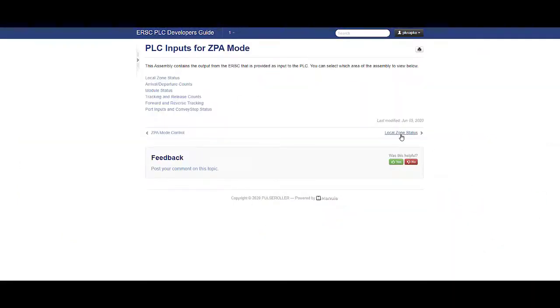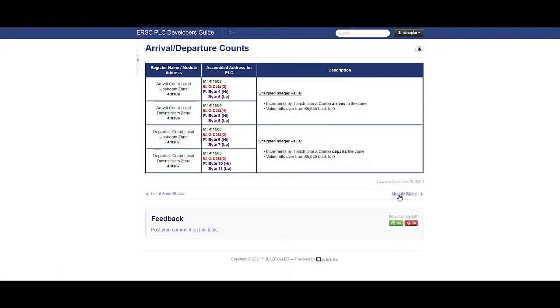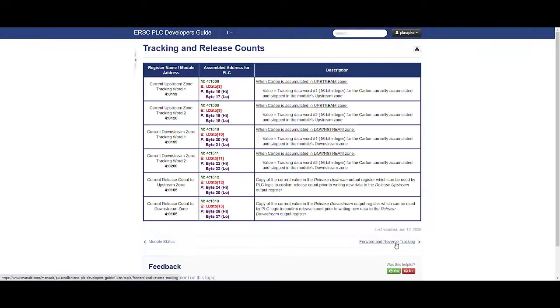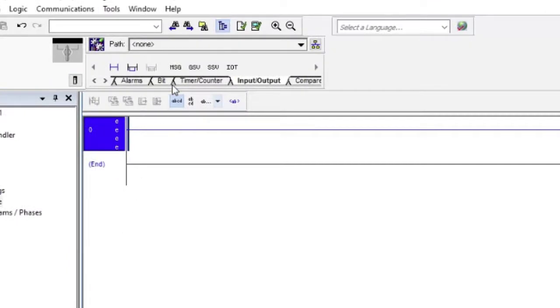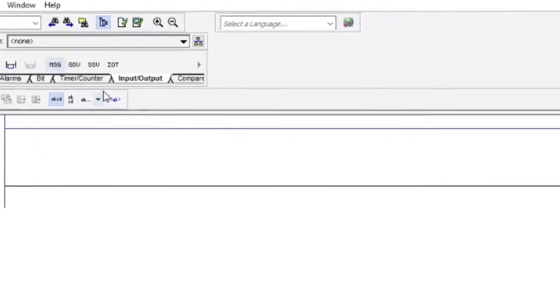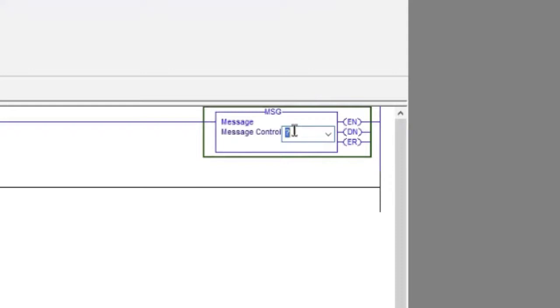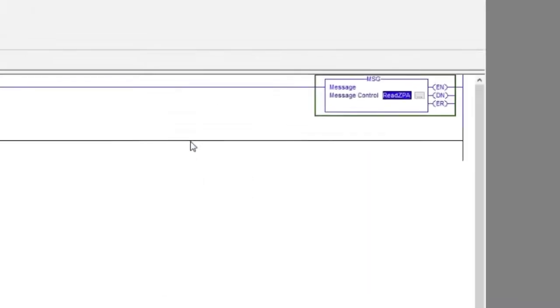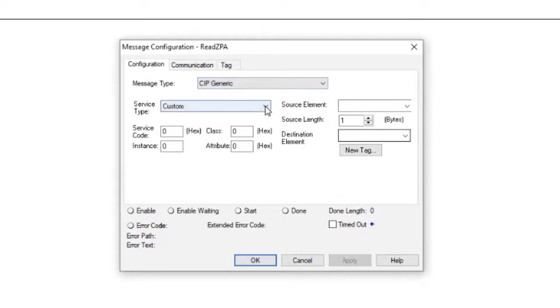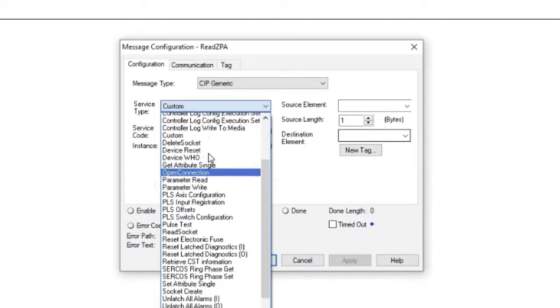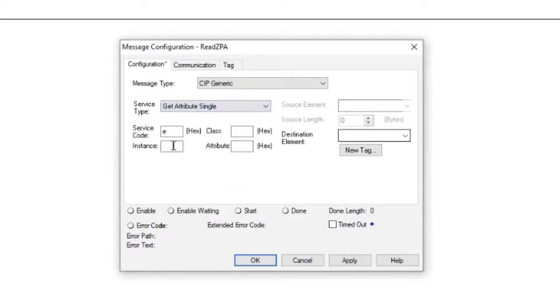What we want to do here is read the entire 21 Register ZPA input assembly instance from the module and place the data into a controller tag integer array. Place the message instruction on a rung and enter a name for the controller tag that will control the instruction. For this example, we're calling it Read ZPA. Now that the message has a controller tag created, we can configure the instruction. The message type is CIP Generic. The service type is Get Attribute Single. The instance happens to be the assembly instance value we want to read from the module, so we enter 105.